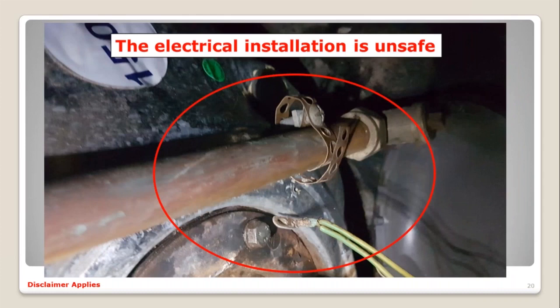You can also see that the bonding was done onto the cold water pipe, but the earthing was not connected back to the bonding. And this is the part where we need to be very careful to not leave the installation unsafe. Next slide. In other words, Alan, if I look at that one, what I understand is that because the earth wire is not connected to the bonding, it doesn't help at all. That continuity doesn't go back to the safety components. It doesn't go back to the trip switches. So even though there's bonding between the pipes, you might end up getting shocked all the same.